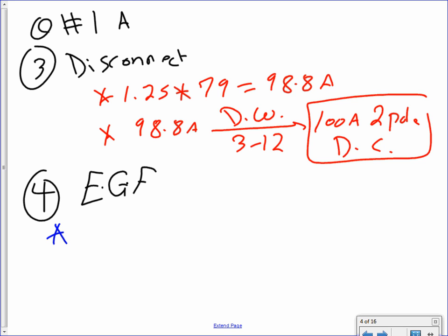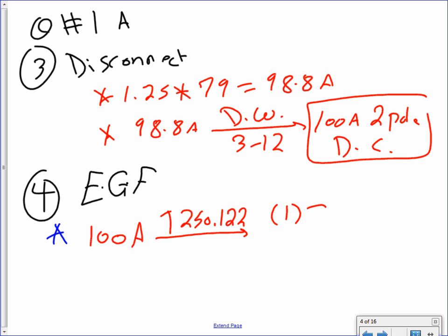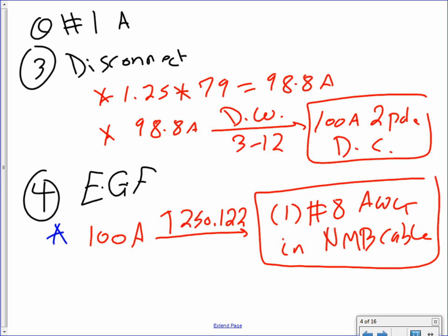Equipment grounding conductor, very easy. You take the 100 amp fuse, it's always based on the fuse, guys. And you go to table 250.122. And when you go there, it's only one column there. And by the way, there are two, but copper and aluminum. Unless I tell you aluminum, it's always what? Copper. So you go to the copper, and in the copper department, you can have a number 8 AWG in your NMB cable. I will remind you guys, we're pulling cables here. So that will be, you really will be sized inside your cable.